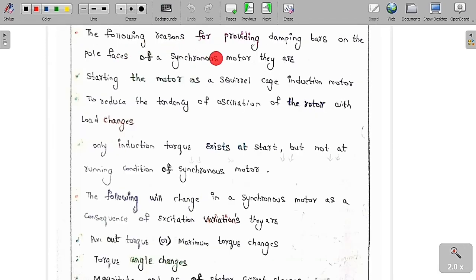The following are the reasons for providing the damping bars on the pole faces of a synchronous motor. They are basically for starting the motor as a squirrel cage induction motor, and to reduce the tendency of oscillation of the rotor with load changes. Only induction torque exists at the start, but not at running conditions of a synchronous motor. See, I already told you the basic function of damping bars in a synchronous motor.